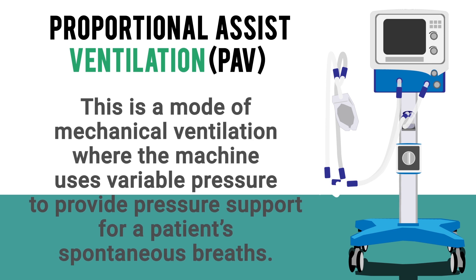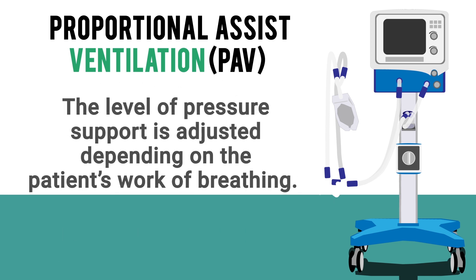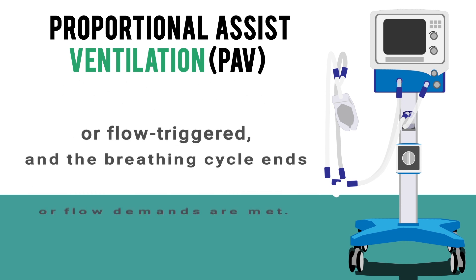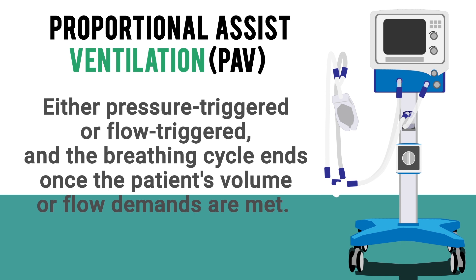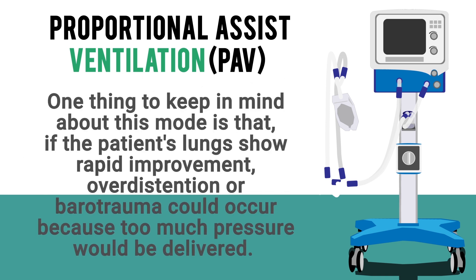PAV, or Proportional Assist Ventilation, is a mode where the machine uses variable pressure to provide pressure support for the patient's spontaneous breaths. The level of pressure support is adjusted depending on the patient's work of breathing. PAV can be pressure-triggered or flow-triggered, and the breathing cycle ends once the patient's volume or flow demands are met. One caution: if the patient's lungs show rapid improvement, overdistention or barotrauma could occur because too much pressure would be delivered.